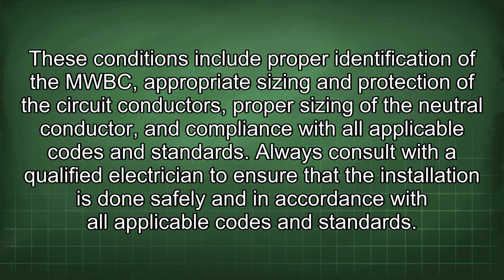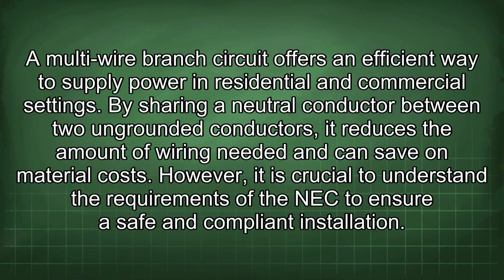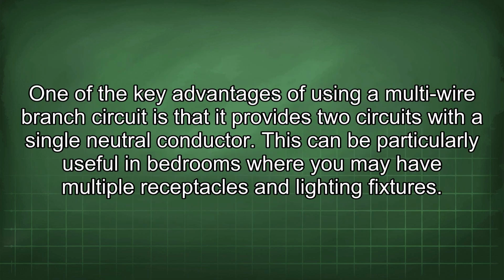A multi-wire branch circuit offers an efficient way to supply power in residential and commercial settings. By sharing a neutral conductor between two ungrounded conductors, it reduces the amount of wiring needed and can save on material costs. However, it is crucial to understand the requirements of the NEC to ensure a safe and compliant installation. One of the key advantages of using a multi-wire branch circuit is that it provides two circuits with a single neutral conductor. This can be particularly useful in bedrooms where you may have multiple receptacles and lighting fixtures.